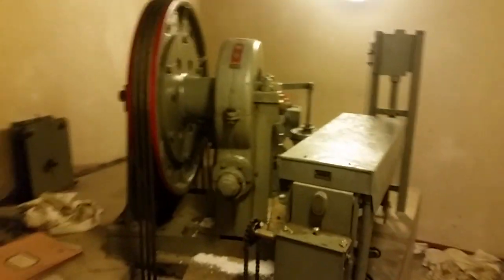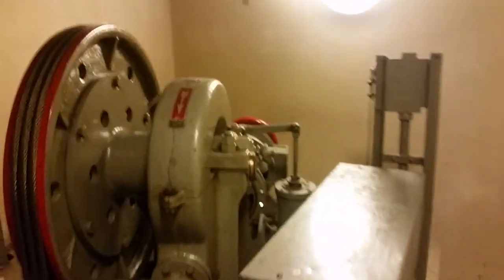And here we've got it — 1953. It's a very old motor elevator, with a motor here: 3.2 kilowatts, 3 phase, 400 volts. There are level switches here. Here we've got the contactors, relays for where the elevator should go — there's an up contactor and a down contactor. And back here we've got some selenium rectifiers, a transformer, nicely wired. There's some kind of resistor there, a capacitor, some smaller capacitors, and another selenium rectifier.